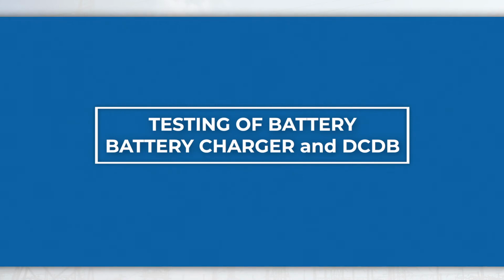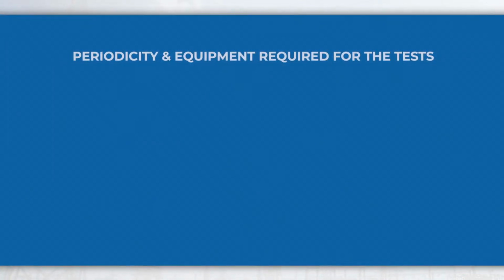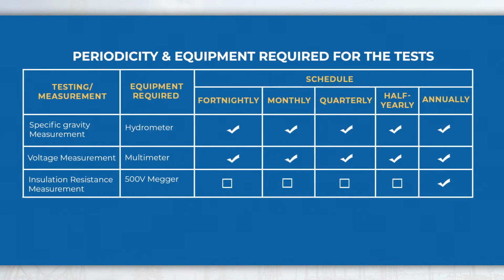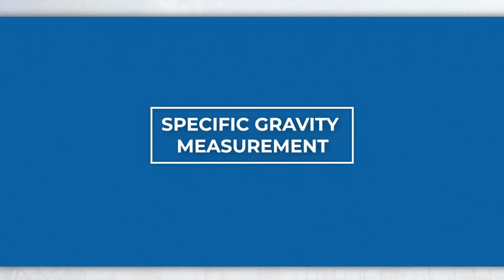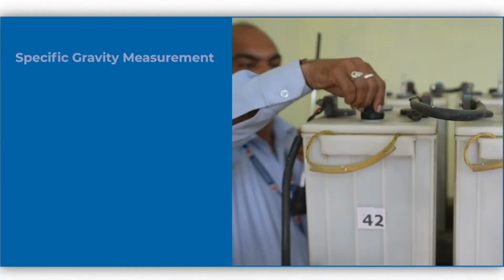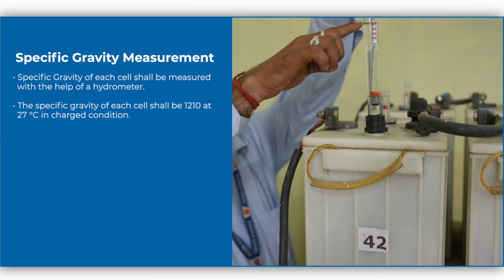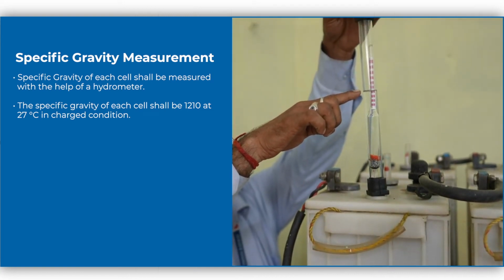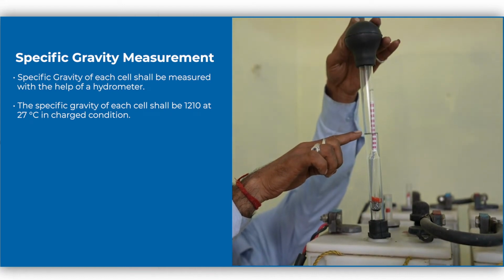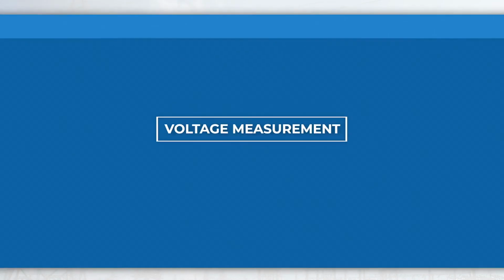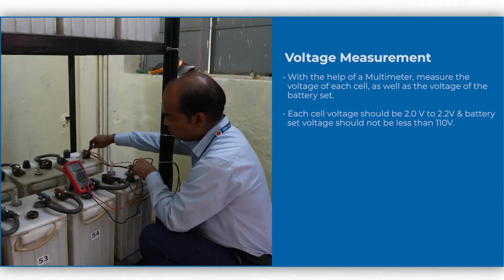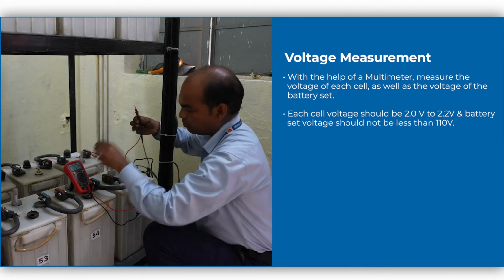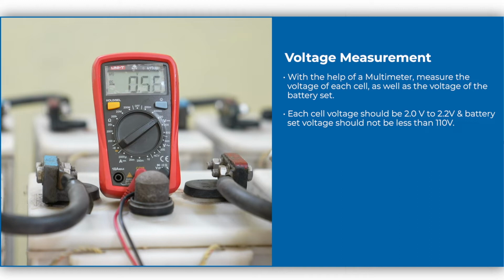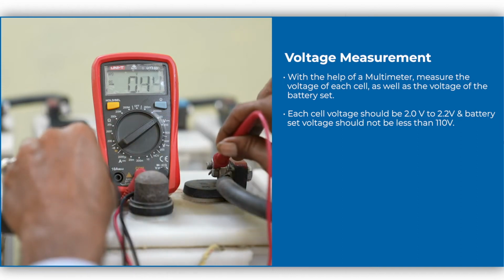Testing of battery charger and DCDB. As per the maintenance schedule, these tests shall be carried out at regular intervals mentioned in this table. Specific gravity measurement. Specific gravity of each cell shall be measured with the help of a hydrometer. The specific gravity of each cell shall be 1210 at 27 degrees Celsius in charged condition. Voltage measurement. With the help of a multimeter, measure the voltage of each cell as well as the voltage of the battery set. Each cell voltage should be 2 volt to 2.2 volt and battery set voltage should not be less than 110 volt.